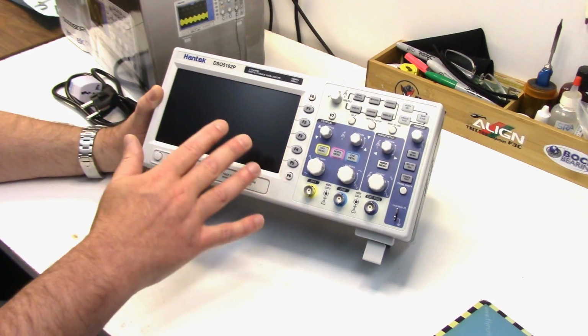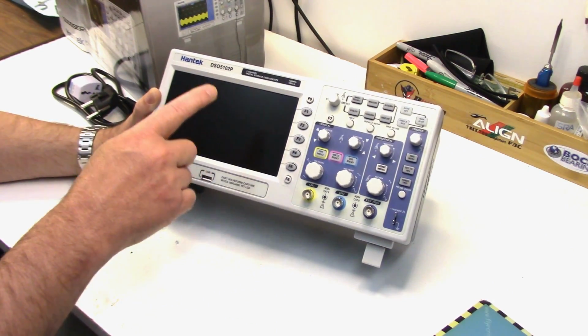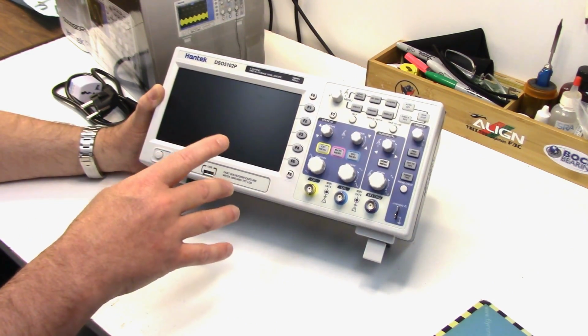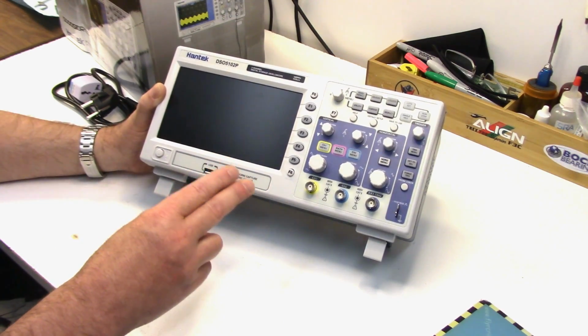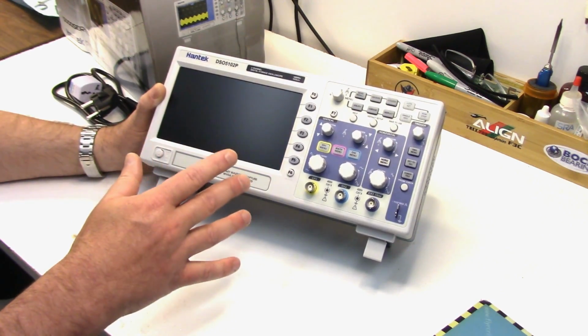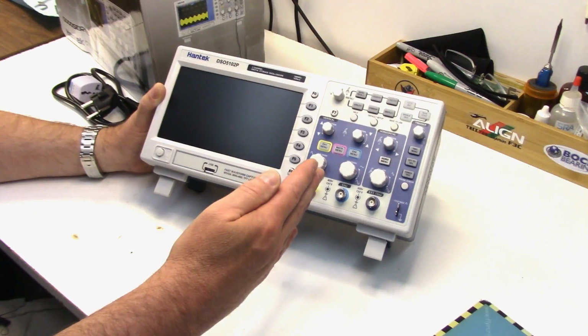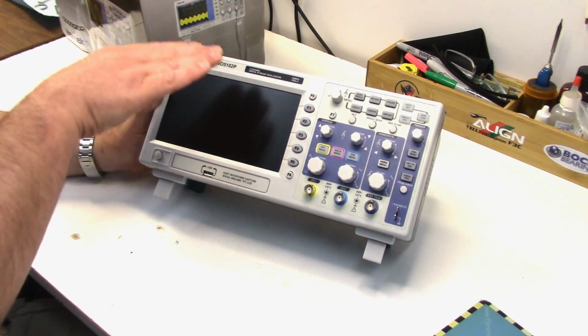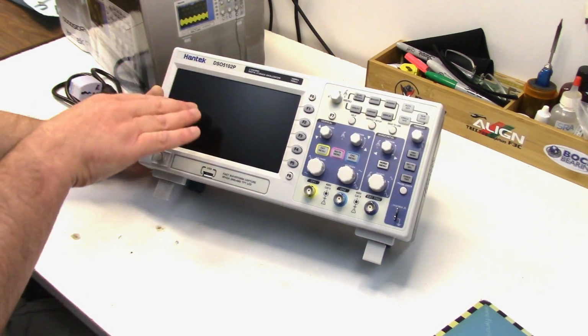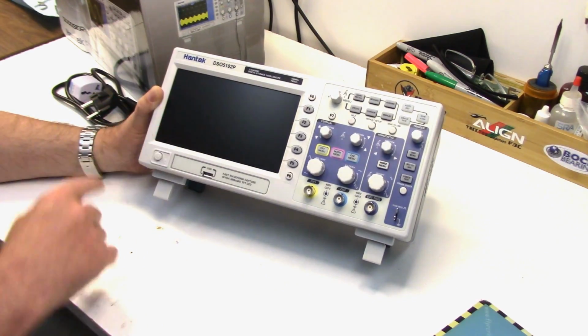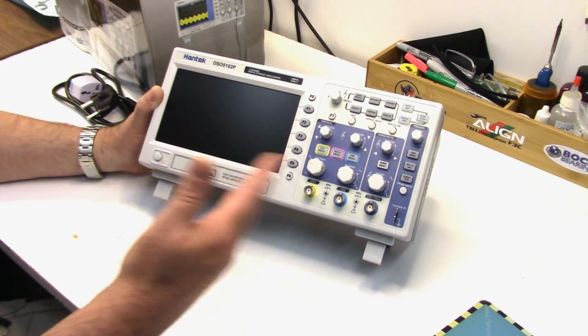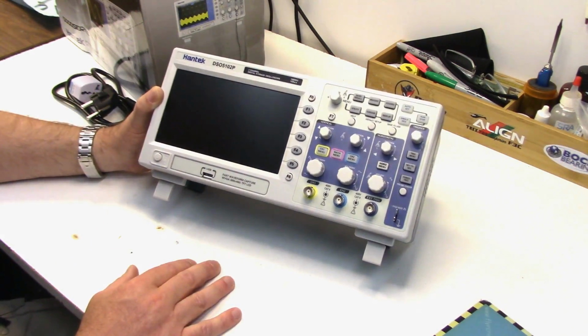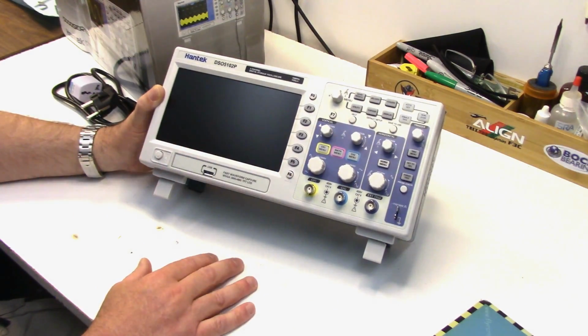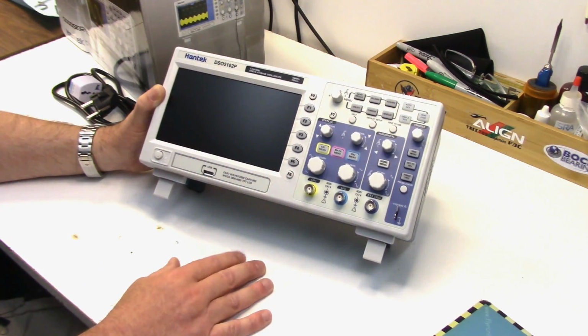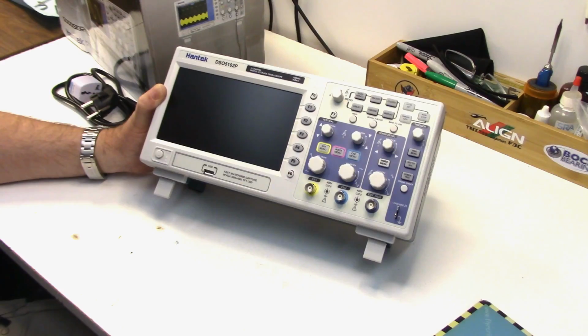The general rule of thumb when selecting a scope's bandwidth is to pick it at least 4 times higher than what you measure. 5 times would be ideal. Now you can certainly measure higher bandwidths, but you lose attenuation, so your voltage will drop as you're measuring higher frequencies. So the general rule of thumb is 4 to 5 times. And rarely do I even get into the megahertz frequency range. I'm usually always checking stuff in kilohertz.